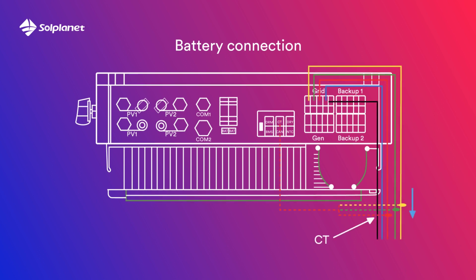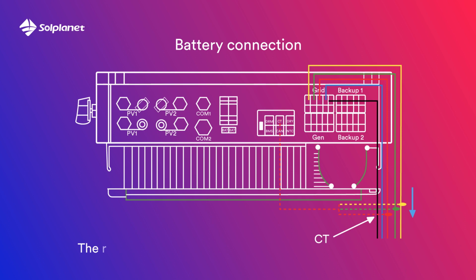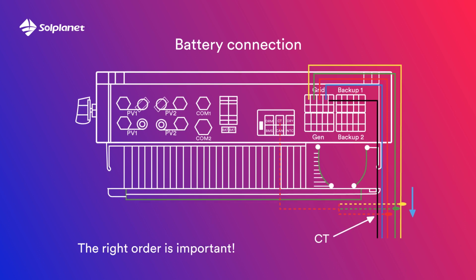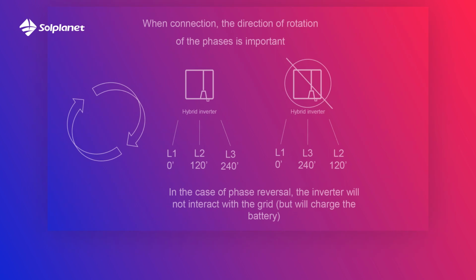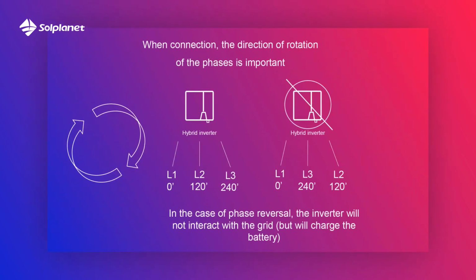Remember to put on current transformers in the right order. The correct sequence of the current transformers is important. The load sources should be connected here. The sequence of phases is important. In case of wrong sequence, the inverter should display an error and it will not work with the grid.